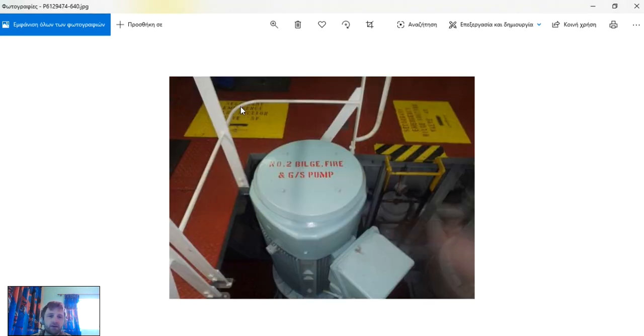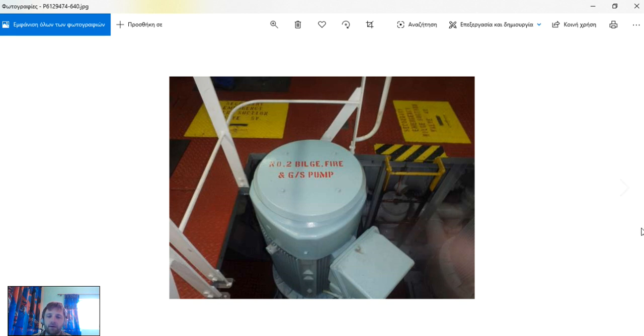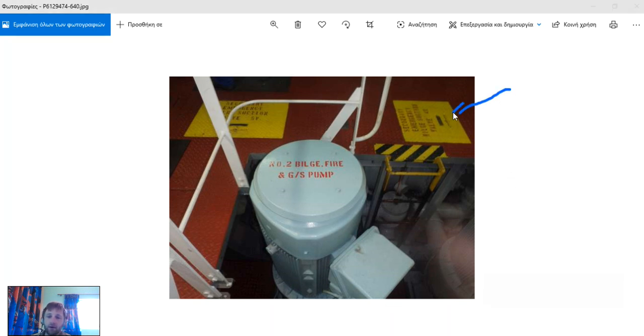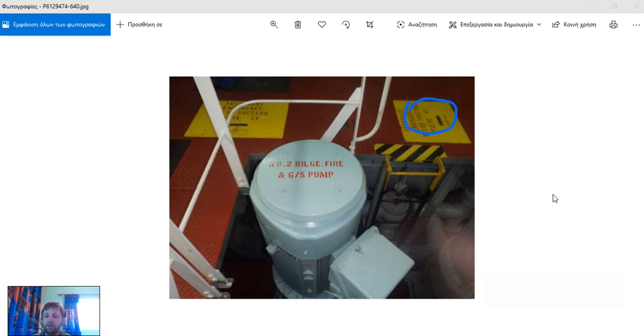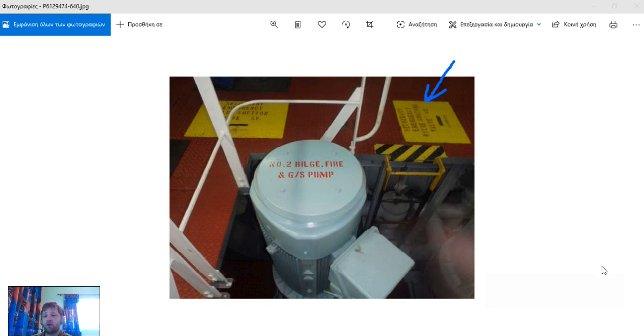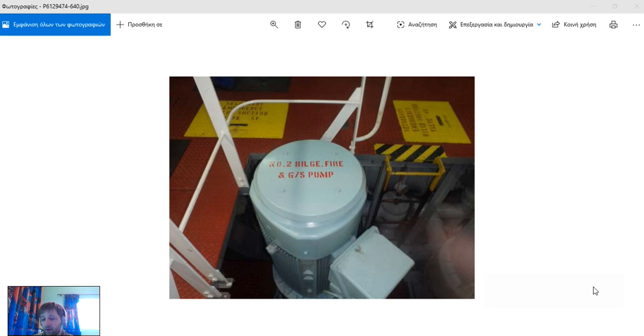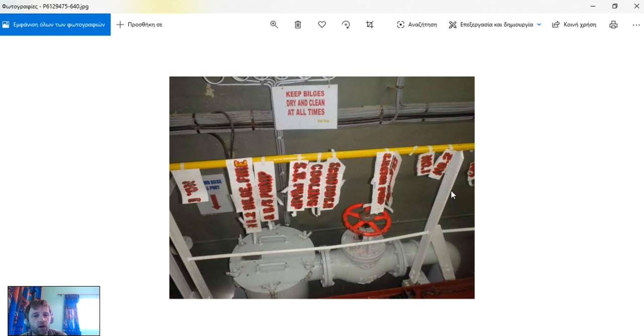As you can see here, the emergency suction valve has a number. It's really easy to locate. Be sure these covers are not stuck by the paint because sometimes what happens is somebody paints new and all the paint has stuck these covers. It's really difficult to open them if you try to run at the moment that the emergency situation happened. It will be already a big loss of time and that is sure.